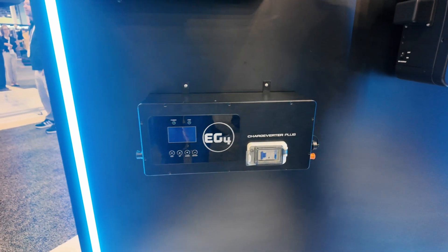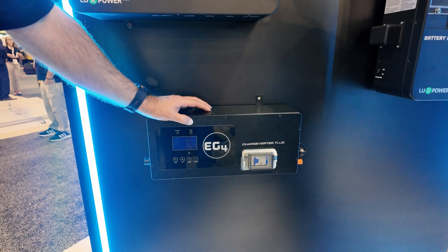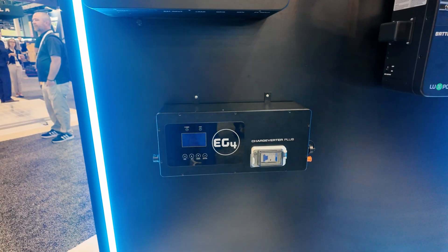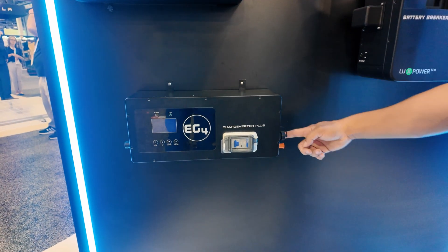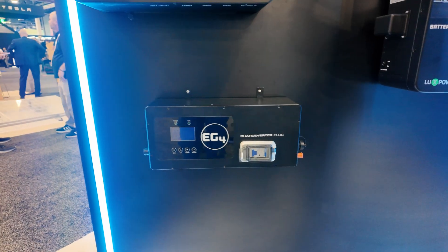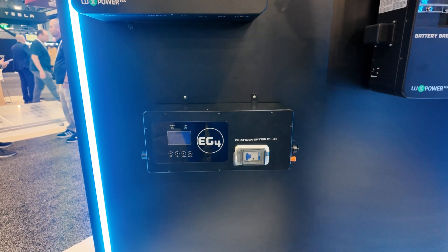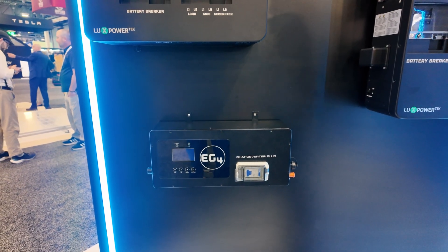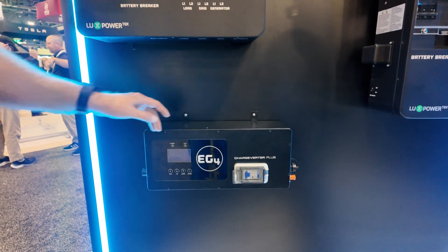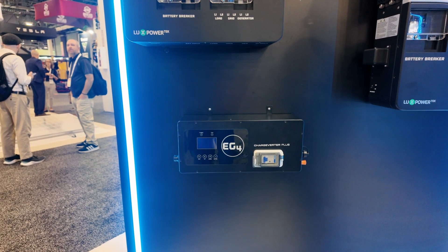They've got another version of the Chargeverter coming out, and this one is going to be UL listed — I think class B certified and IP54 rated. So you can permanently mount this on installations that are getting inspected. In the past, because it wasn't UL listed, there were problems with AHJs not accepting the Chargeverter being permanently mounted. They went through and made modifications to get it UL listed, so now you can have it permanently mounted and wired into your installation.